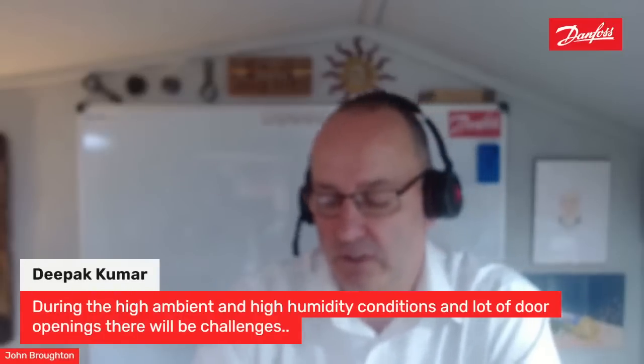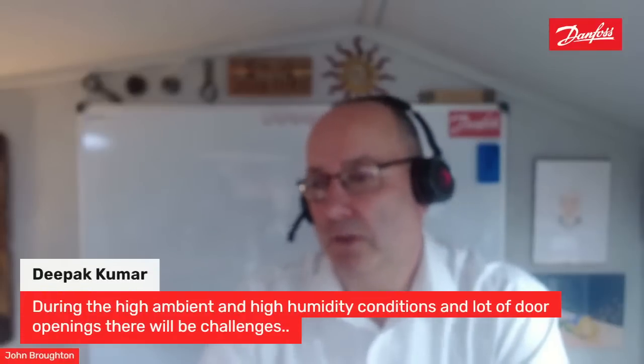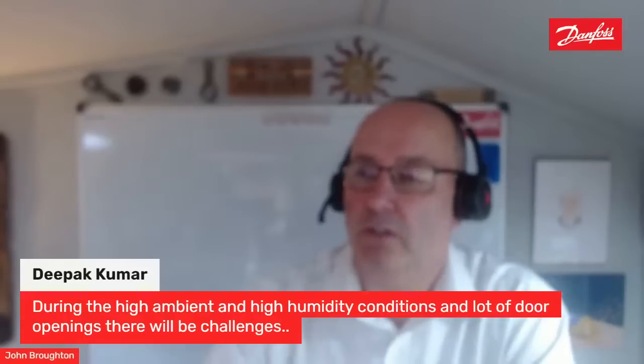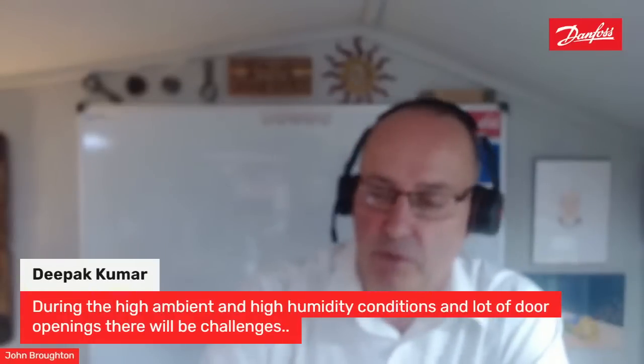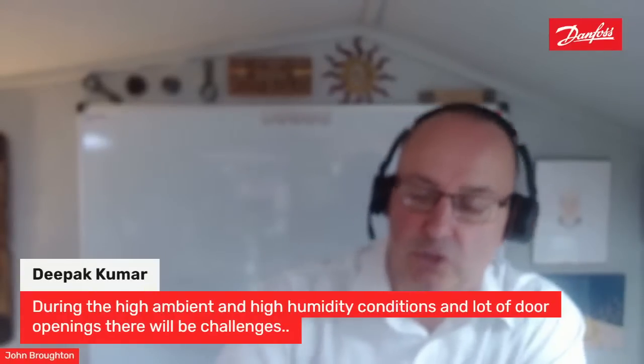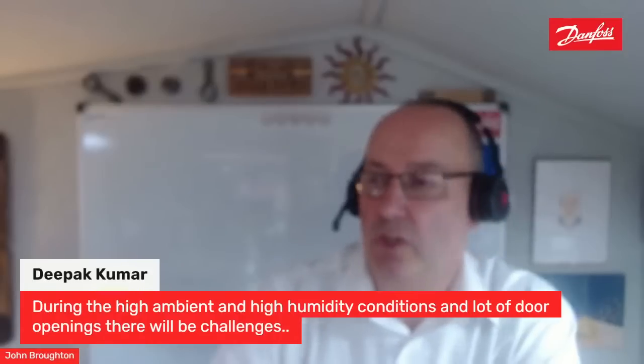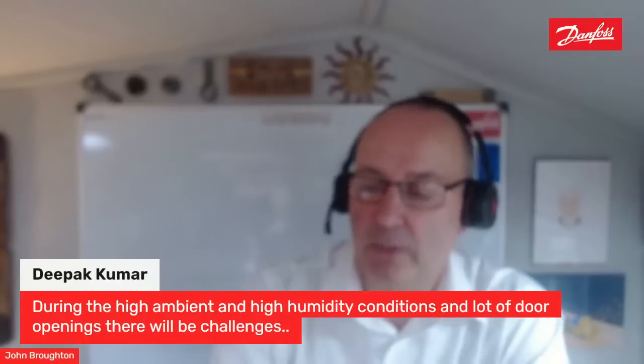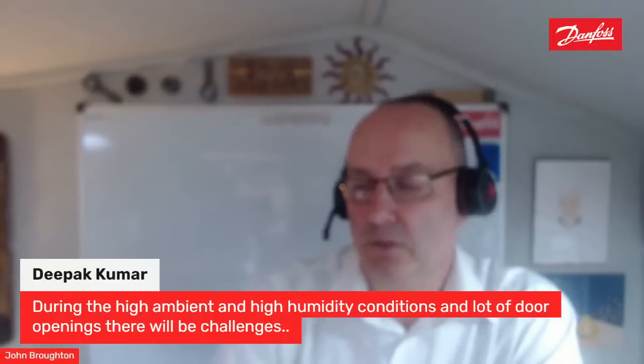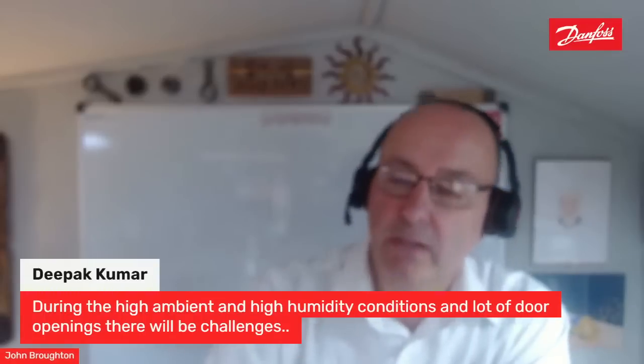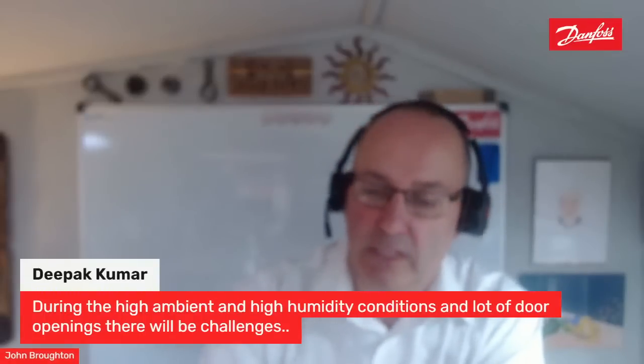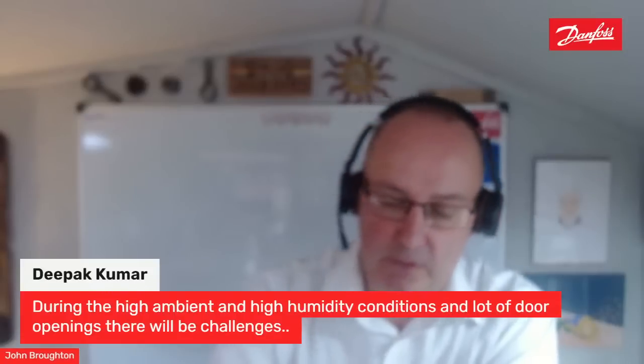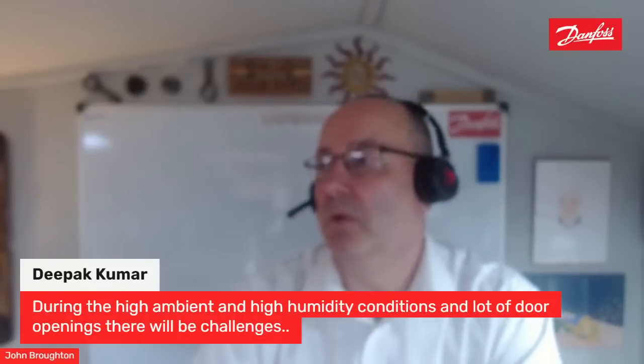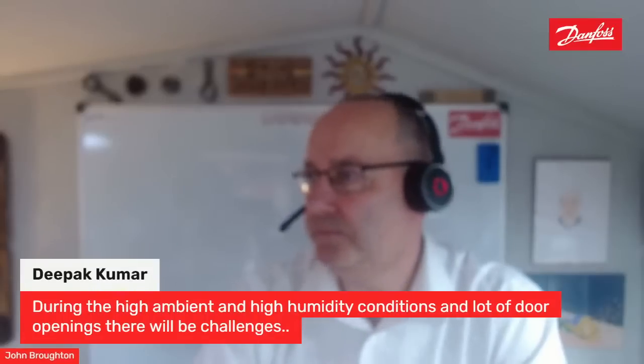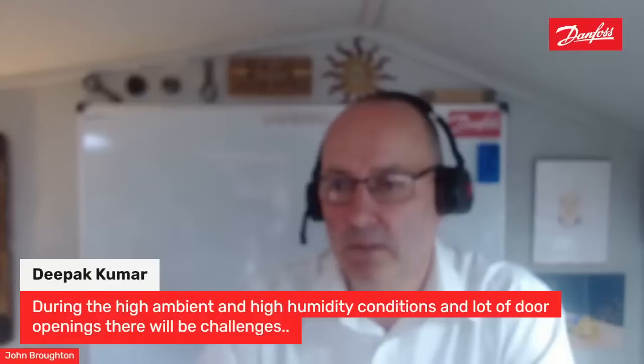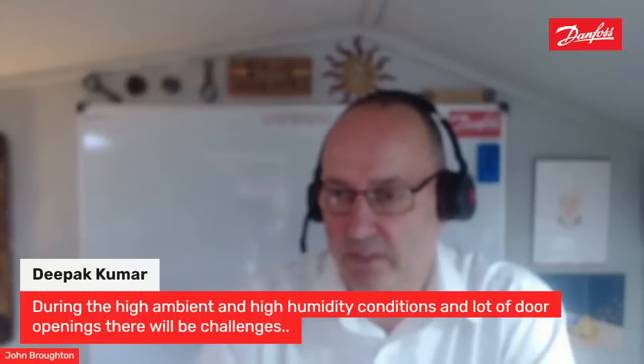So then you've got to look at things on your door. If they're going to keep the door open, then maybe we need a door curtain, a PVC strip curtain for example, to try and stop that exchange of air between outside and inside. We can also have an air blower across the front of the door, so we maintain a curtain of blown air between the inside and outside, minimizing that warm moist air going up inside the cold room and getting on the cooler.